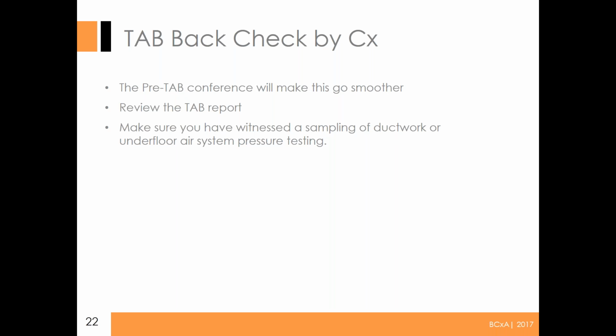Yes, that's a good example of why you shouldn't do that. You should have a percent, or a fixed CFM, or something like that instead. Unfortunately, they don't divvy it up like that because they can't. Instruments just aren't that accurate, especially at low flows. They could be, say, if you're under 100 CFM, but not with a hood, not with a typical hood.